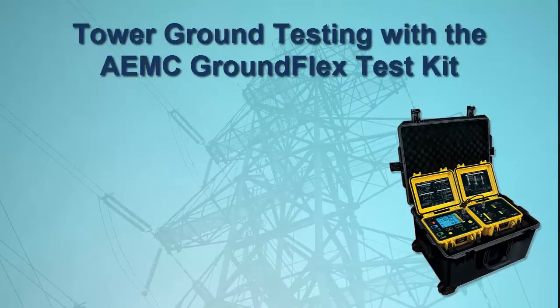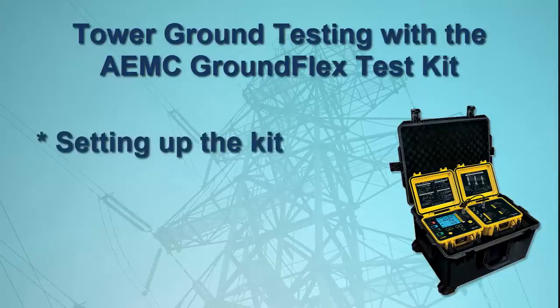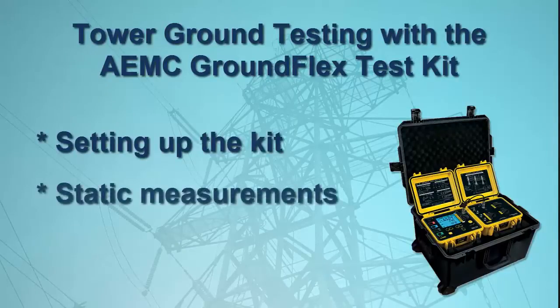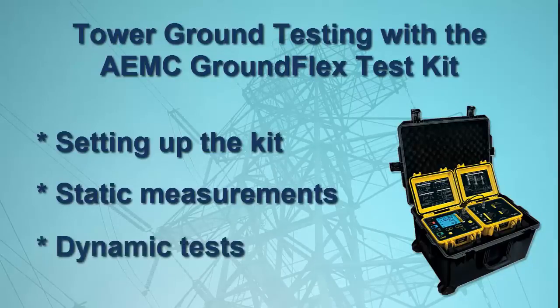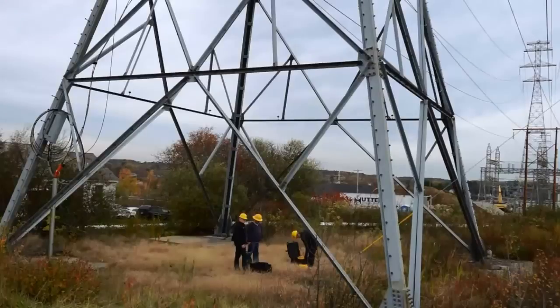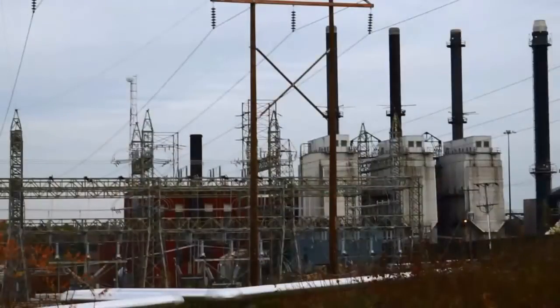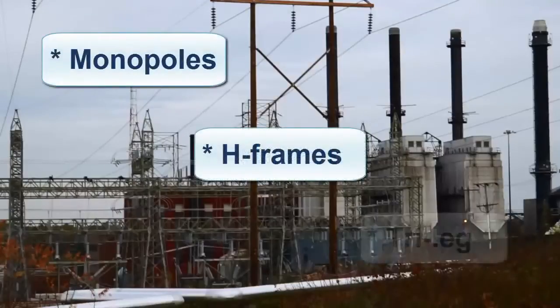We start by explaining how to set up the kit to obtain static readings such as passive resistance and leakage current. We then dynamically test the total tower resistance, initially at a baseline frequency, and then via a sweep from low to high frequencies. Our test subject in this video is a four-legged lattice tower. However, the GroundFlex Field Kit can also test monopoles, H-frames, and tri-leg towers.